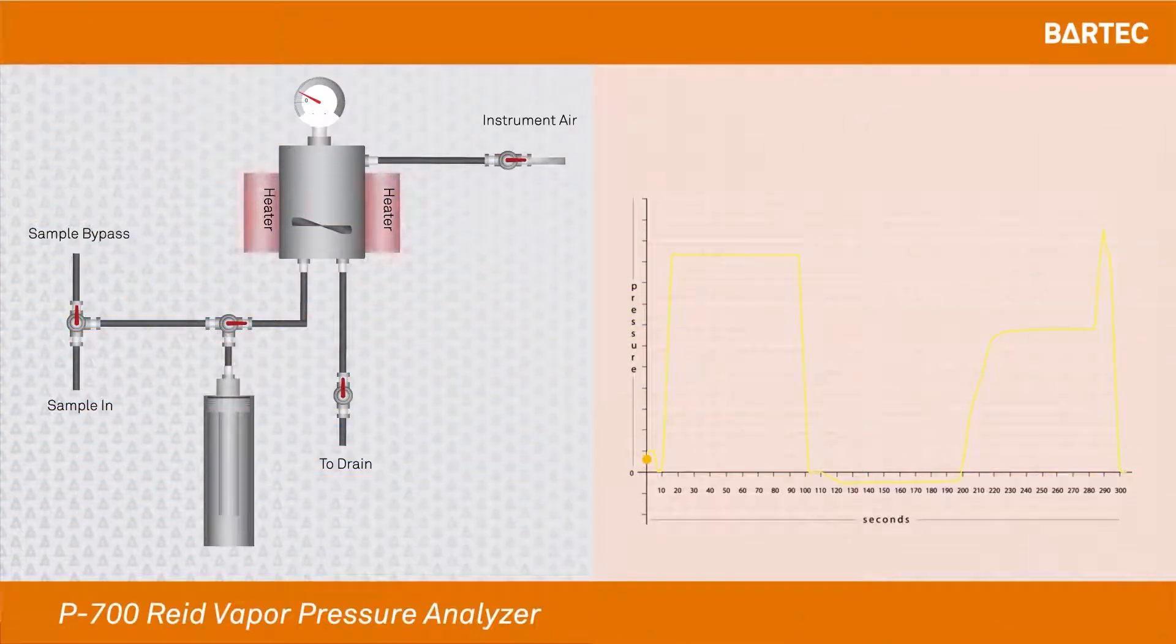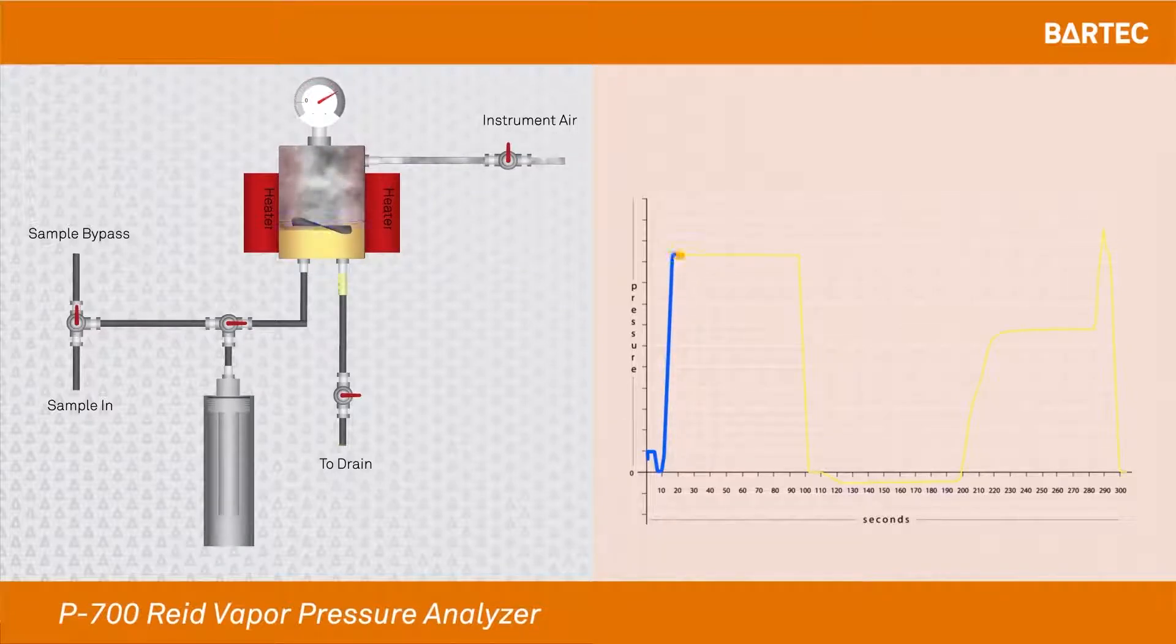In this animation, you will see to the right a graph of the pressure gauge as the pressure changes inside the measuring cell. The first step of the measurement is to bring the measuring cell to 100 degrees Fahrenheit at which it will be maintained throughout the entire process. Once the cell has reached 100 degrees Fahrenheit, we will open the drain to remove any vapors left inside the measuring cell.